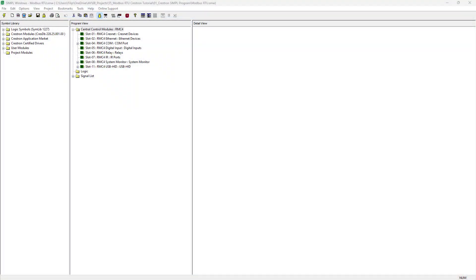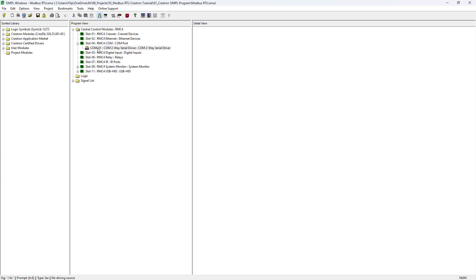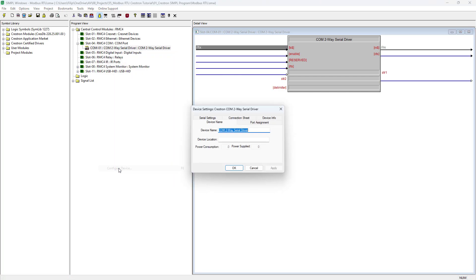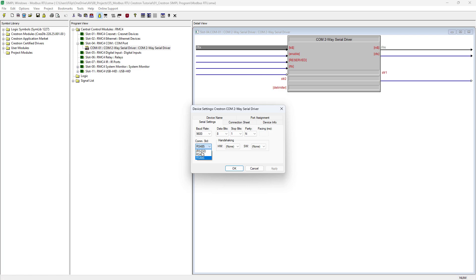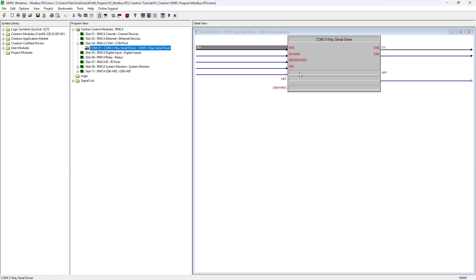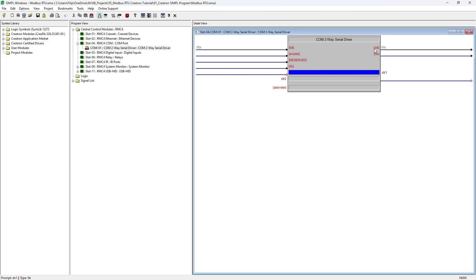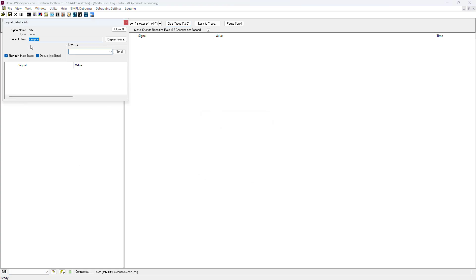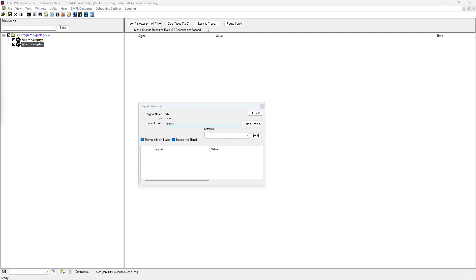Now let's switch to SIMPL Windows. Open the COM port configuration by right-clicking and selecting configure device. Set the protocol to RS-485, and enter the same serial parameters we used earlier. For this demo, we'll only use the TX and RX serial signals. After compiling and uploading the program, we can open the SIMPL debugger to test our commands. Remember the Modbus commands we saved earlier? Let's use one now — we'll enter the read command for the temperature and send it through the TX signal.